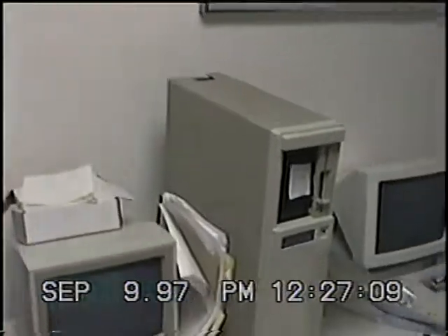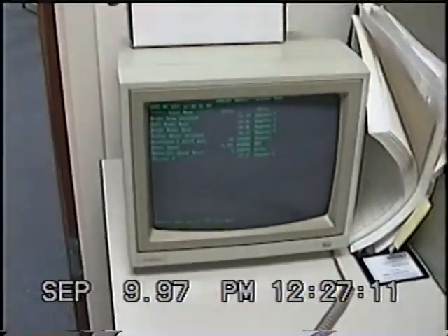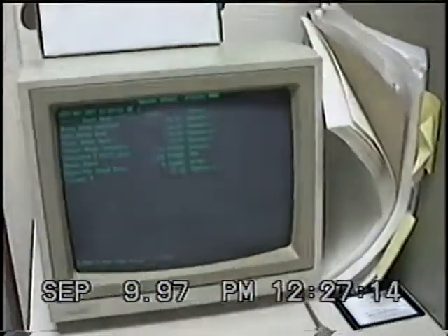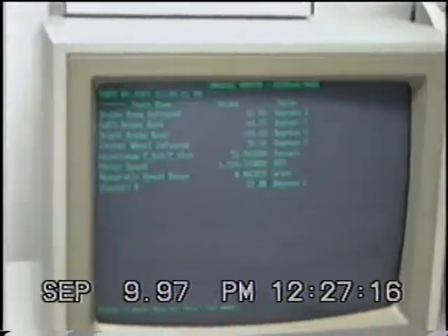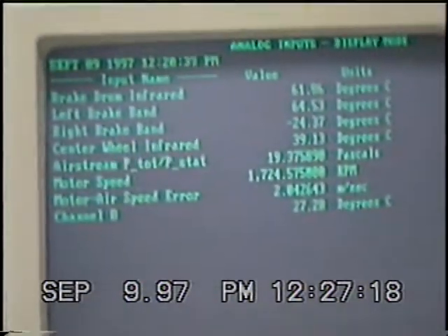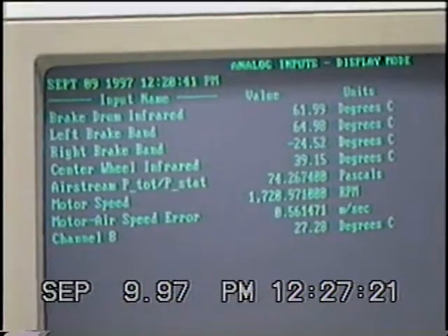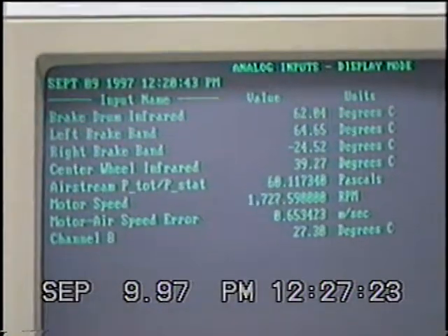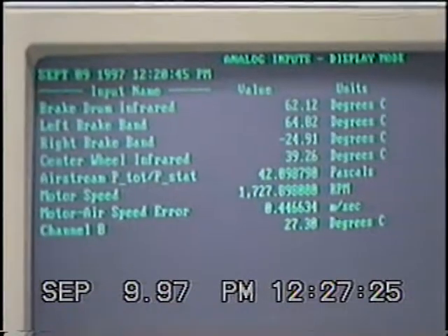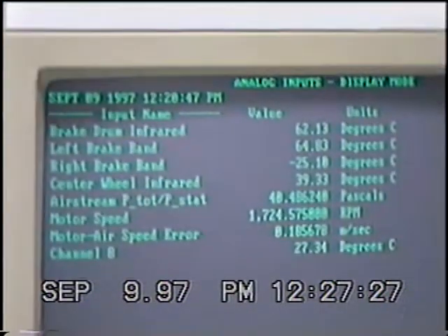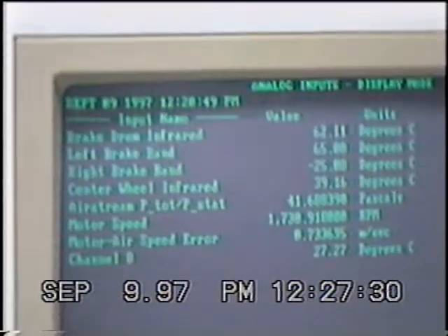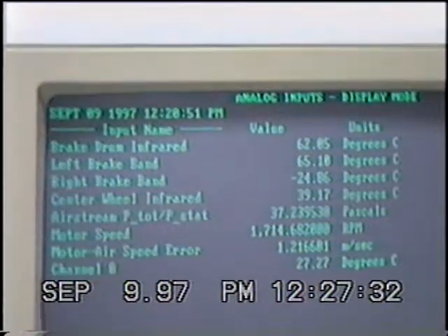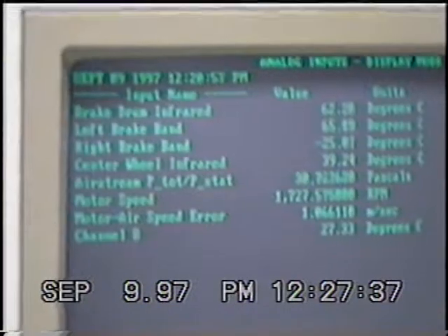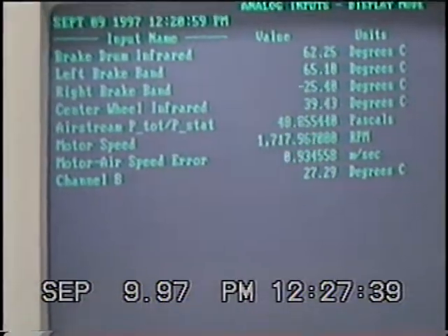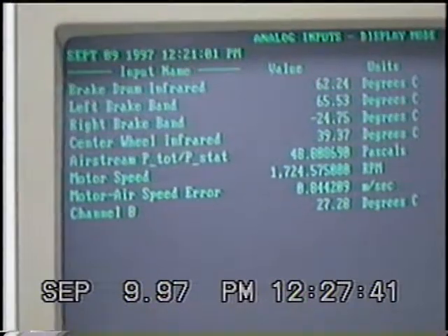I mentioned we were having some trouble with one of the thermocouples, and that being for the right brake band. Basically, that's why we have two of them, to give us some redundancy, because measurement of either one is just fine. You see that the brake bands are, for this particular test, getting up around 60 degrees C. I'll let you do the conversion. The surface temperature of the brake drum that runs against the wheels is also up to about 60 degrees C. But interestingly, the center wheel, infrared, is about 20 degrees lower than that.